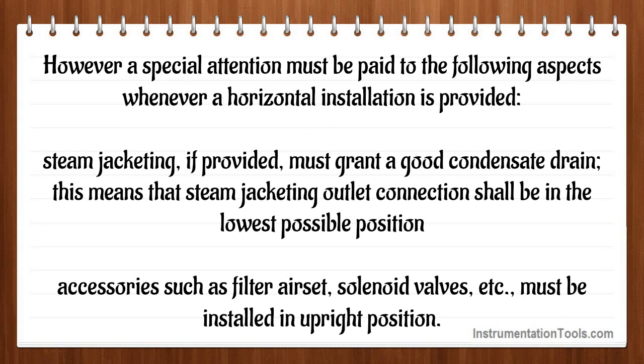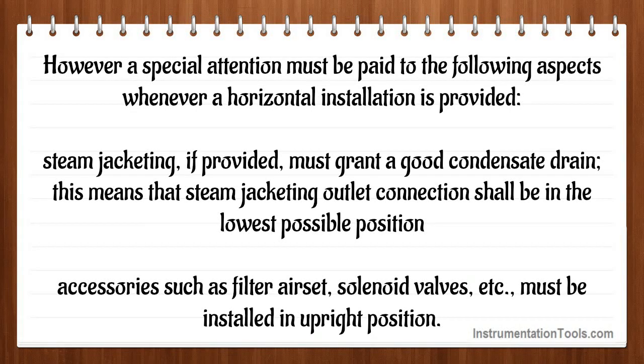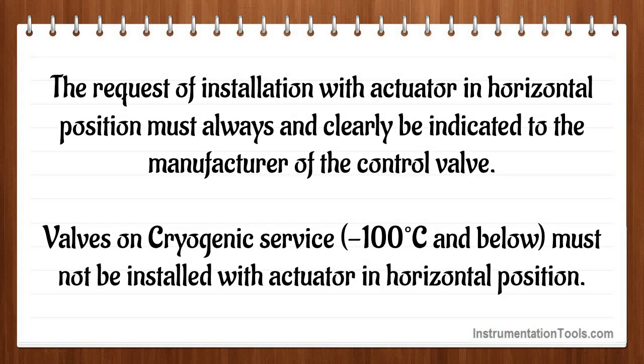However, special attention must be paid to the following aspects whenever a horizontal installation is provided. Steam jacketing, if provided, must grant a good condensate drain — the steam jacketing outlet connection shall be in the lowest possible position. Accessories such as filter, air set, solenoid valves, etc., must be installed in upright position. The request for installation with actuator in horizontal position must always be clearly indicated to the manufacturer of the control valve. Valves on cryogenic service — minus 100 degrees centigrade and below — must not be installed with the actuator in horizontal position.